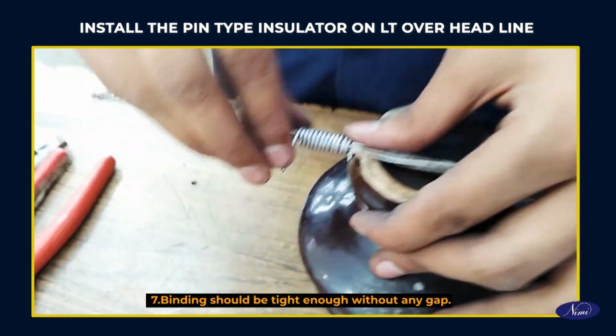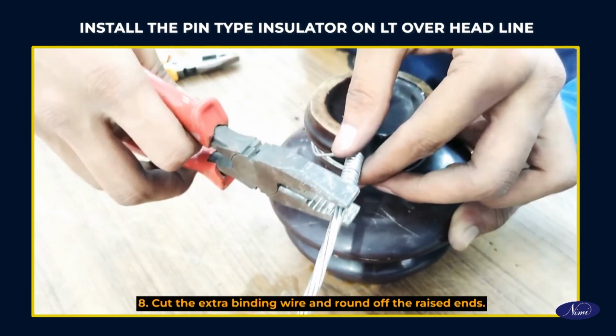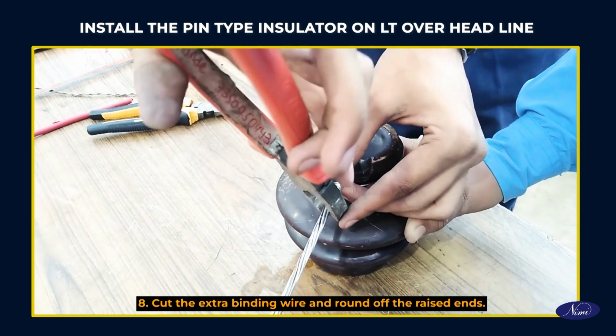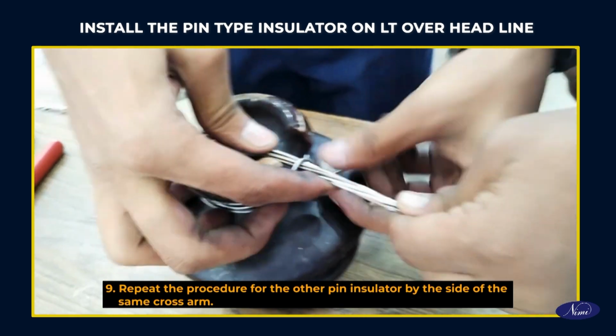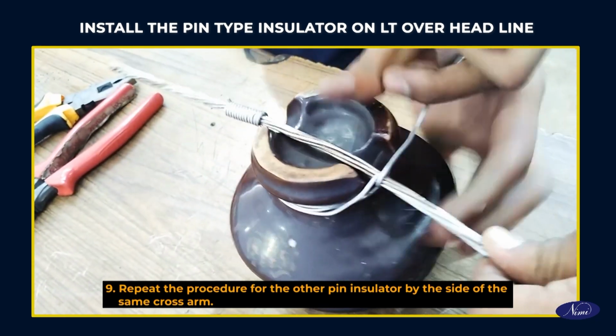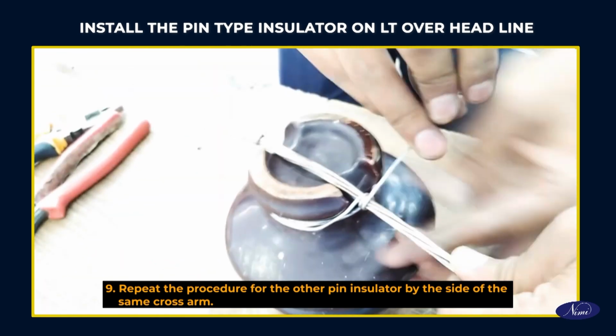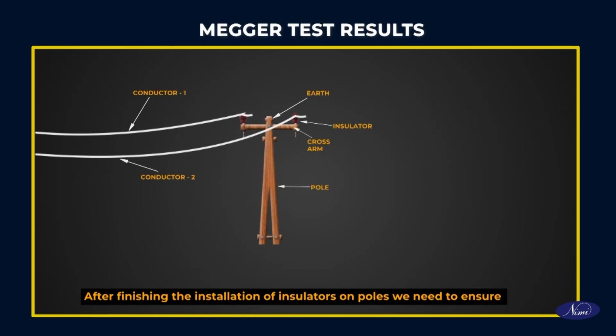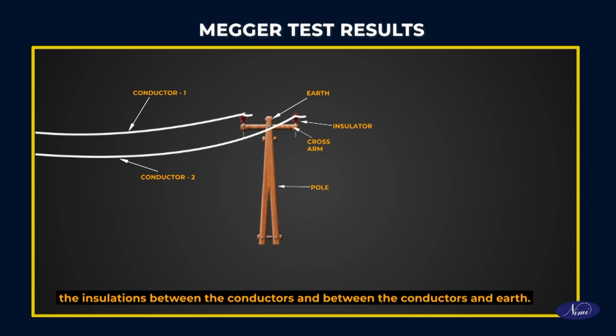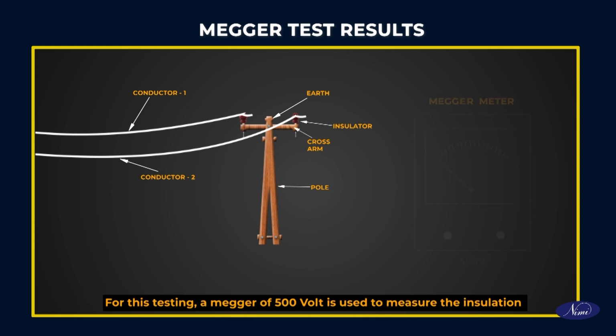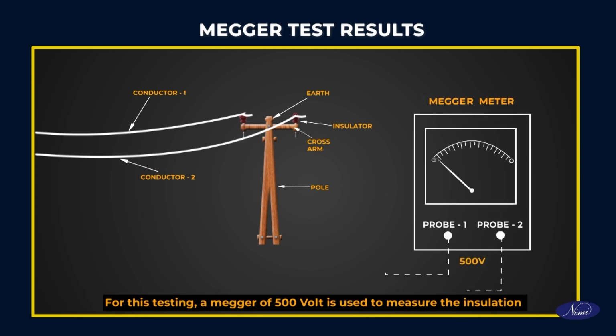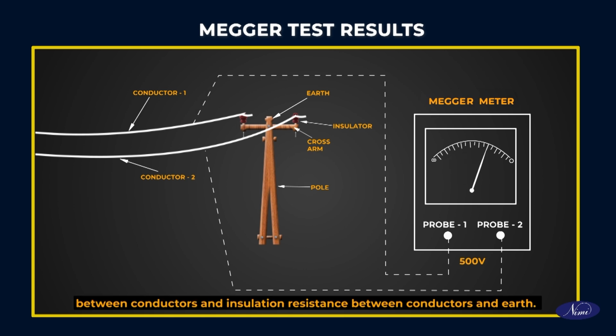Binding should be tight enough without any gap. Cut the extra binding wire and round off the raised ends. Repeat the procedure for the other pin insulator by the side of the same cross arm. After finishing the installation of insulators on poles, we need to ensure the insulation between the conductors and between the conductors and earth. For this testing, a Megger of 500 volt is used to measure the insulation resistance between conductors and insulation resistance between conductors and earth.